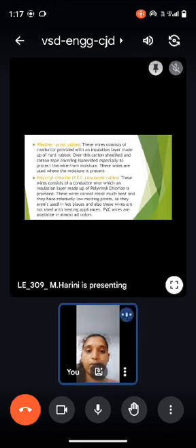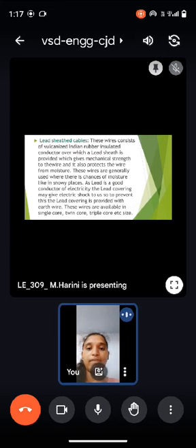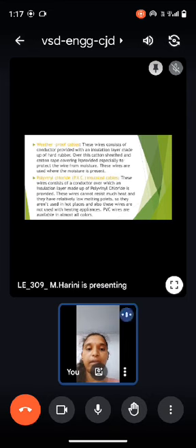PVC cables consist of conductors over which an insulation layer made of polyvinyl chloride is provided. These wires cannot resist much heat and they have a relatively low melting point, so they are not used in hot places, and also these wires are not used with heating appliances. PVC wires are available in almost all colors.